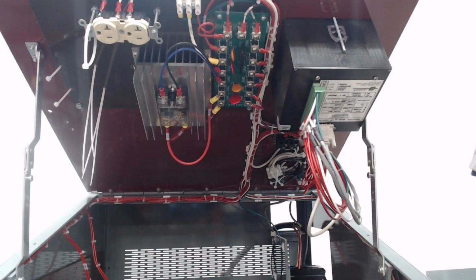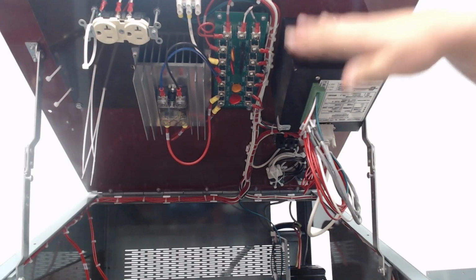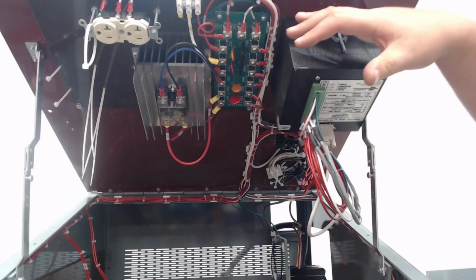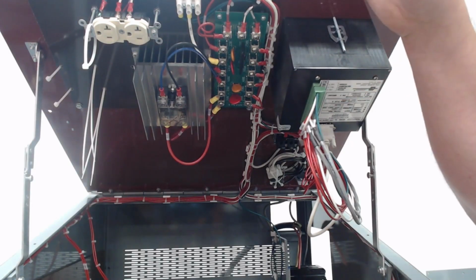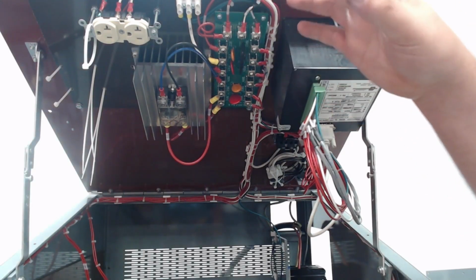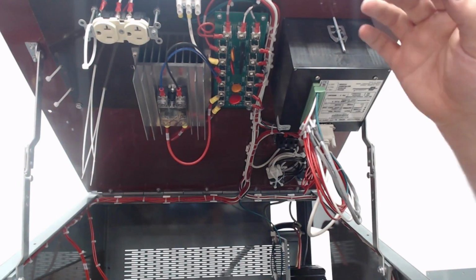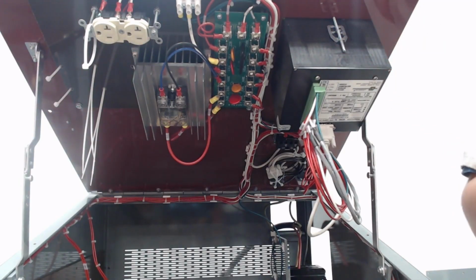For what we're doing right now, we're going to start on the meter not turning on, contactor not turning on, and the unit not ramping up and down. So we're just going to go over the basic controls. The first thing you should do before you do any of this, for either this one or the next setup, check your incoming voltage, make sure it's correct, and I'm going to go ahead and show you.